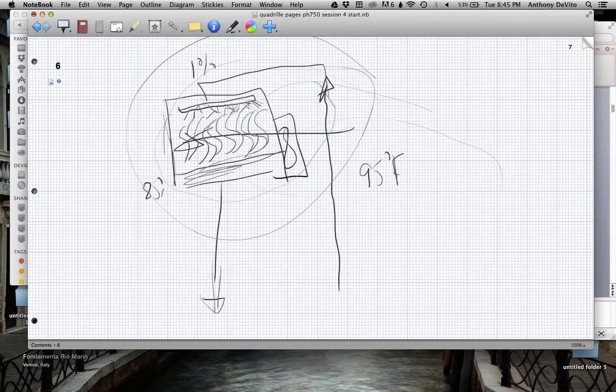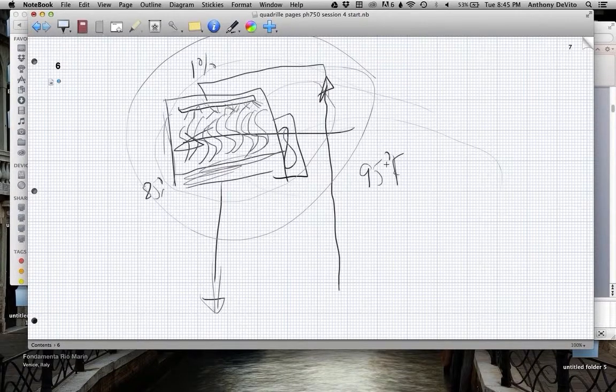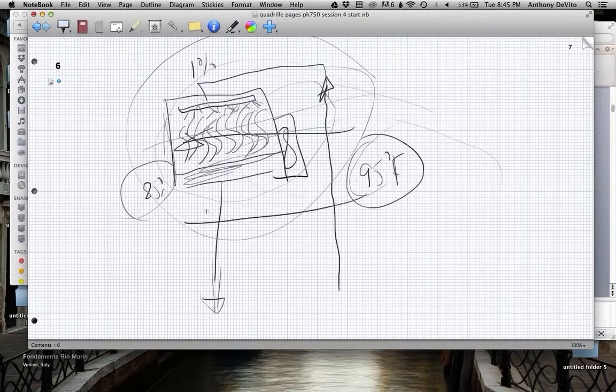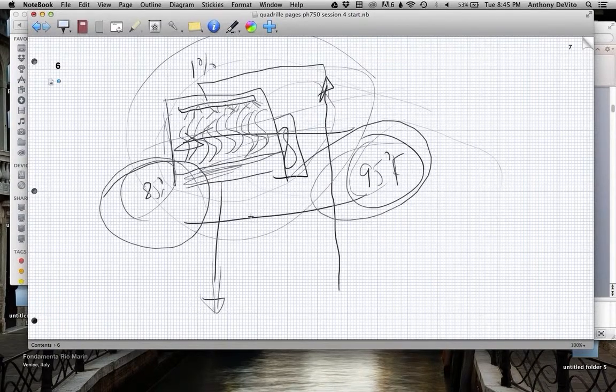So here you go. You've got that cooling tower. Anybody know what bad thing cooling towers are associated with? Legionella, right? Why is it a problem in this particular device? Well, because you're blowing air through it, so all sorts of crap gets filtered out of the air, including bugs, pathogens, mold spores, leaves, and all kinds of other stuff. But there's something important about the cooling tower in particular. The water is between 85 and 90 degrees. On a really hot day, it goes up to 100, 105.